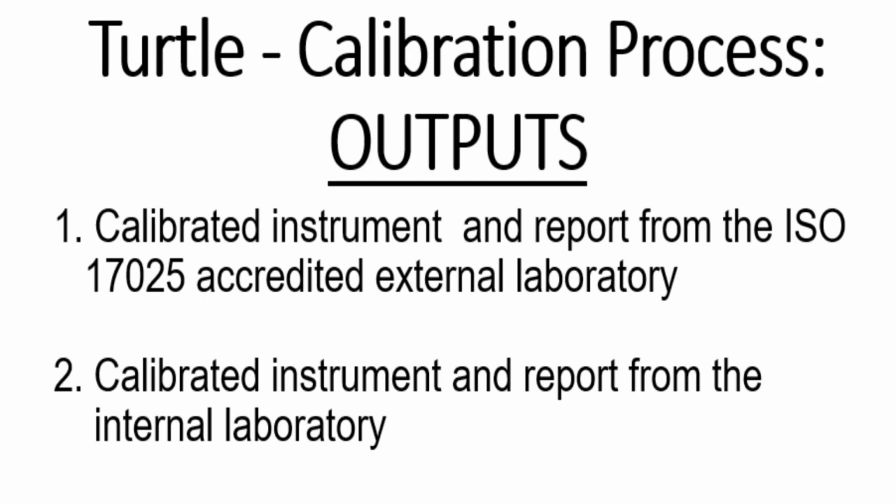When we talk about the outputs, here I have specified 2 key outputs. One is the calibrated instrument and the report, if it is an external laboratory, that it should be 17025 accredited, and if it's an internal calibration, so again the calibrated instrument with a report from the internal laboratory.